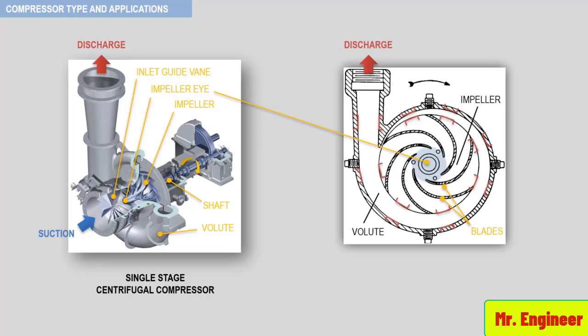The gas is then conducted around the volute housing in an ever-increasing escape channel. As the pathway increases, the velocity decreases and even more pressure is added to the gas, again according to the Bernoulli principle. Then, the gas leaves the compressor at discharge pressure, prepared to overcome the resistance in the system.